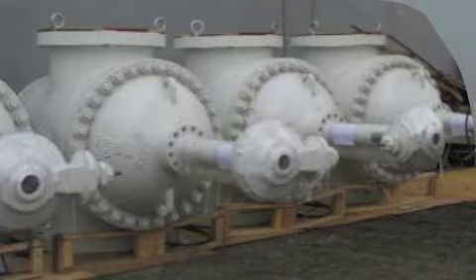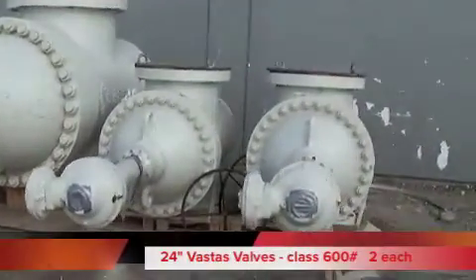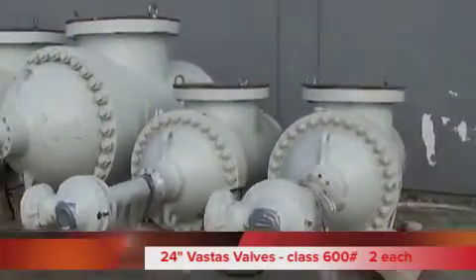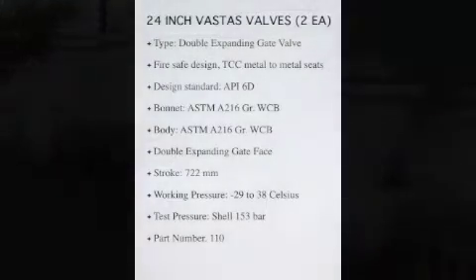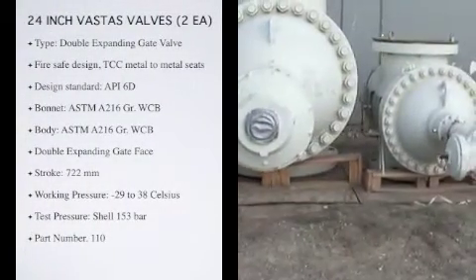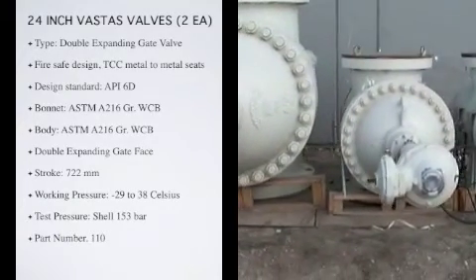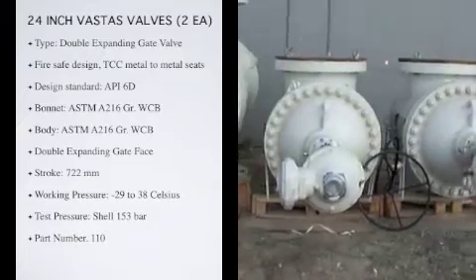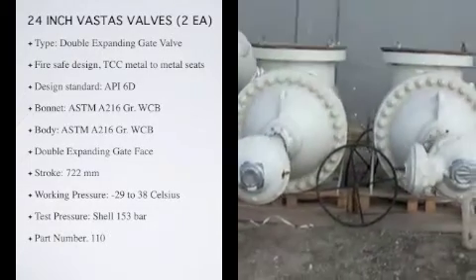The 24-inch Vastas valve is Class 600. Type: double-expanding gate valve, double-block and bleed. Fire-safe design, TCC metal-to-metal seats with emergency lubricant seal. Design Standard API 6D. Bonnet: ASTM A216 Grade WCB. Body: ASTM A216 Grade WCB.